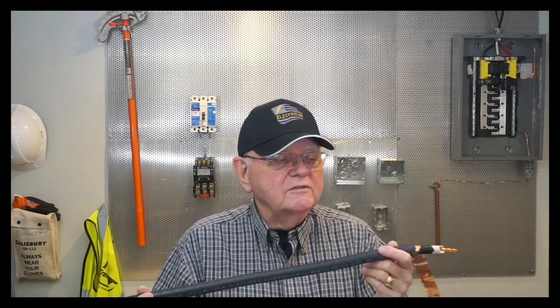The purpose of the copper tape, we're going to ground it probably at both ends, because the way I look at it is you can't keep all the electrons on the inside at medium voltages. You're going to have some of those escape, and you could create a potential difference. So you're going to take this metal sheath, and any electrons that do escape go into the metal sheath, it's connected to ground, and that potential difference then is dissipated into the earth. Medium voltage cable, 2001 to 35,000 volts.